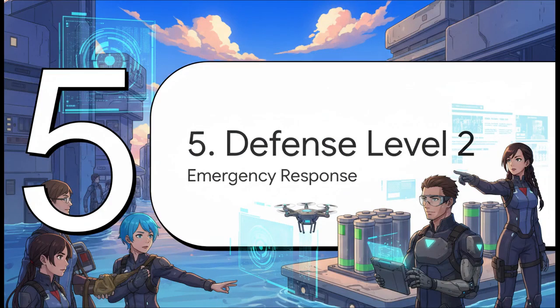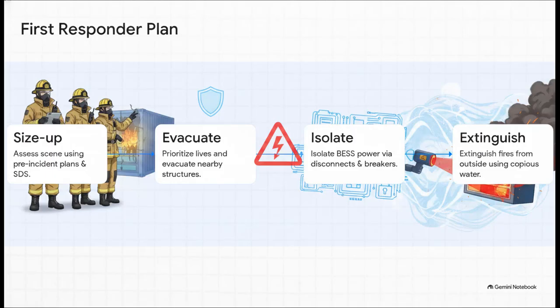Moving to Section 5, Defense Level 2, Response. If all those design precautions fail, the second layer of defense kicks in, relying on first responders to execute a highly tactical action plan. Responders have to methodically work through these steps, treating the situation with extreme caution. We're talking severe risks of electric shock and latent reignition. Because these fires involve complex, dangerous chemistries and energized metal boxes, crews usually operate in full protective gear, using thermal imaging cameras from a very safe distance, prioritizing external containment above all else.